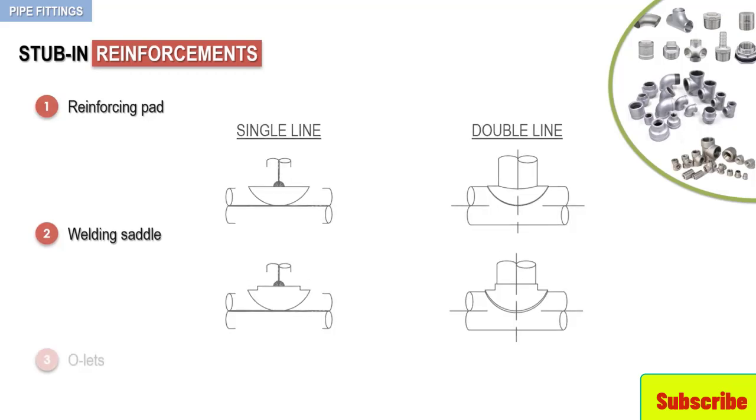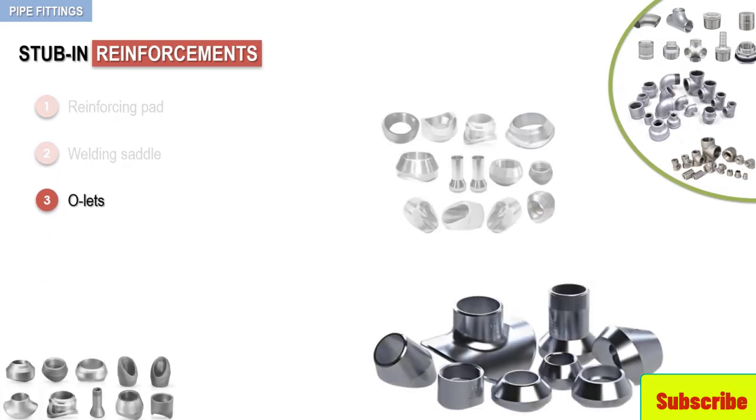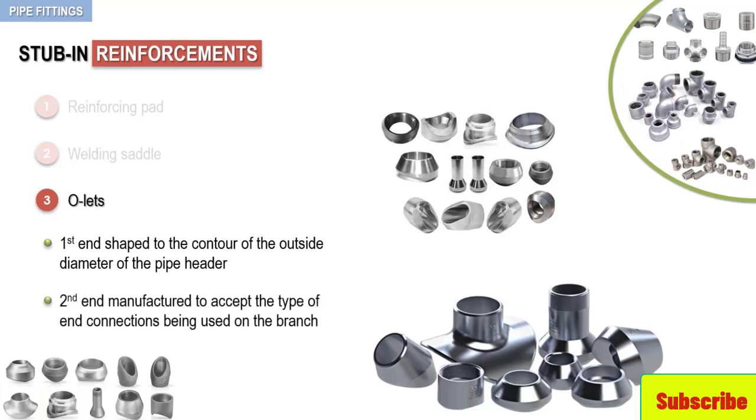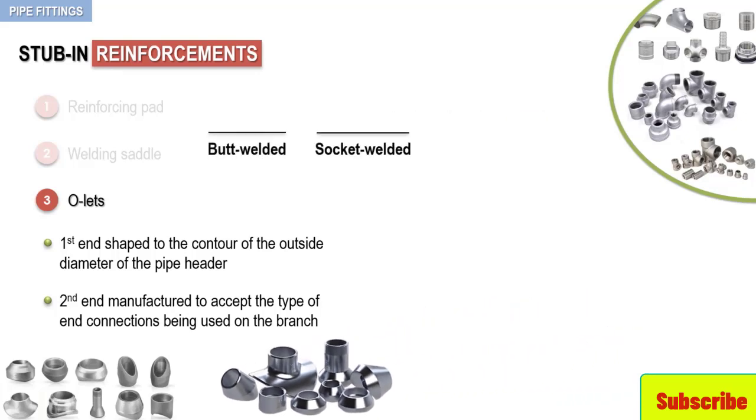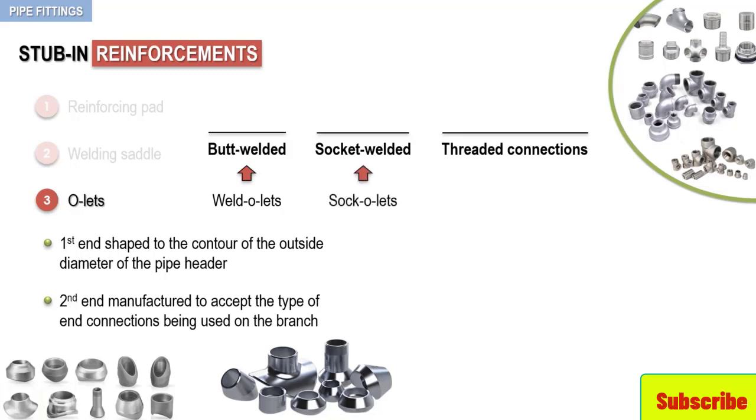The last stub-in reinforcement is O-lets. O-lets are purchased fittings that have one end shaped to the contour of the outside diameter of the pipe header, and the other end manufactured to accept the type of end connections being used on the branch. O-lets are manufactured for butt-welded, socket-welded, and threaded connections. Weld-O-lets are manufactured for butt-weld fittings. Sock-O-lets are made for socket-weld fittings. And thread-O-lets are available for screwed fittings.